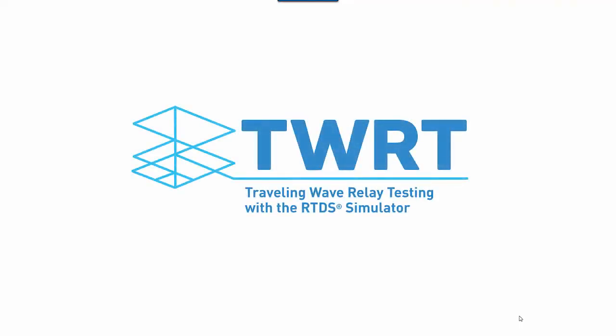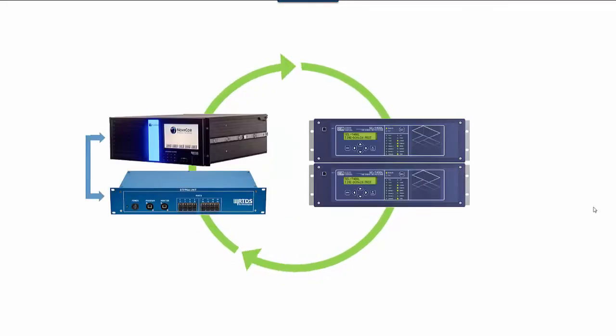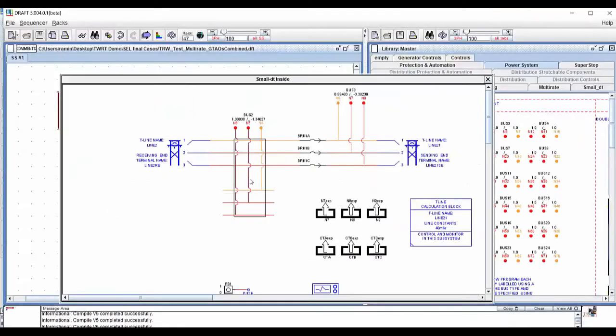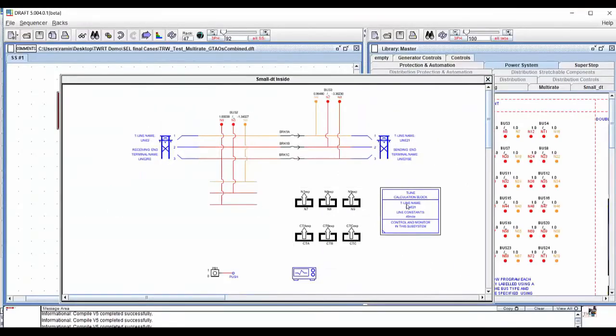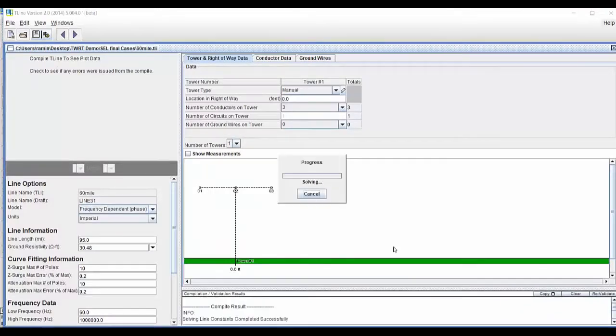With the release of TWRT, we enable our users to comprehensively test traveling wave protection devices in a closed loop. The RTDS simulator is the only tool that offers robust and flexible frequency-dependent transmission line models simulated at the required small time step.